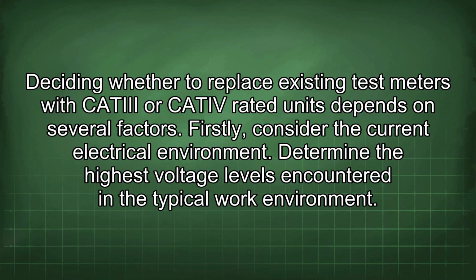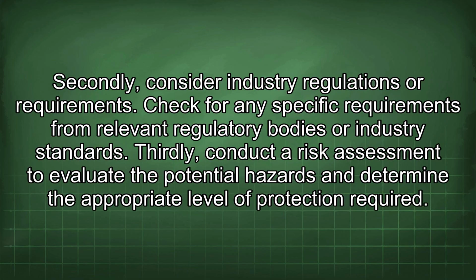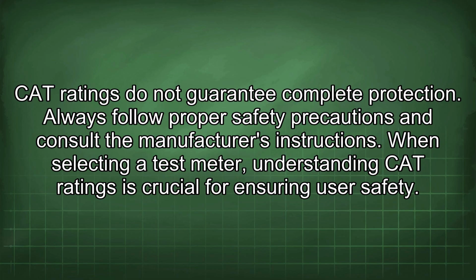Deciding whether to replace existing test meters with CAT III or CAT IV rated units depends on several factors. Firstly, consider the current electrical environment. Determine the highest voltage levels encountered in the typical work environment. Secondly, consider industry regulations or requirements. Check for any specific requirements from relevant regulatory bodies or industry standards. Thirdly, conduct a risk assessment to evaluate the potential hazards and determine the appropriate level of protection required. CAT ratings do not guarantee complete protection. Always follow proper safety precautions and consult the manufacturer's instructions.